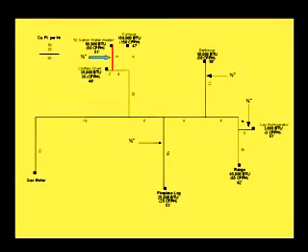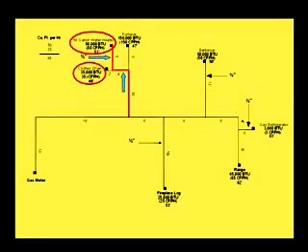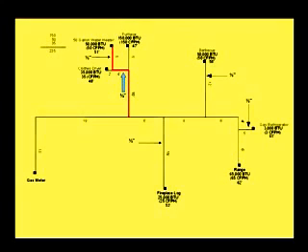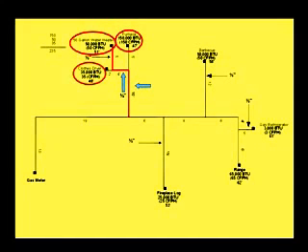The 4-foot section of pipe will be supplying the branch line to the clothes dryer with a demand of 35 cubic feet per hour, plus the 50 cubic feet per hour of the water heater, for a total demand of 85 cubic feet per hour. Refer to table 12-8, 60-foot row — 85 will fit under 137 — and see that a 3/4-inch pipe will accommodate the 85 cubic feet per hour demand for the 4-foot pipe.